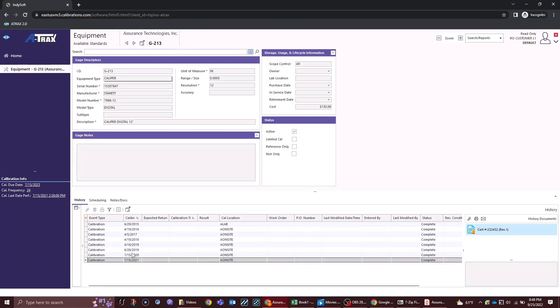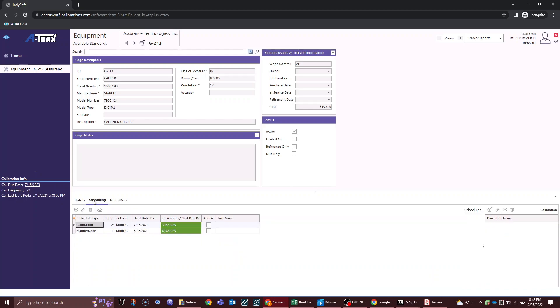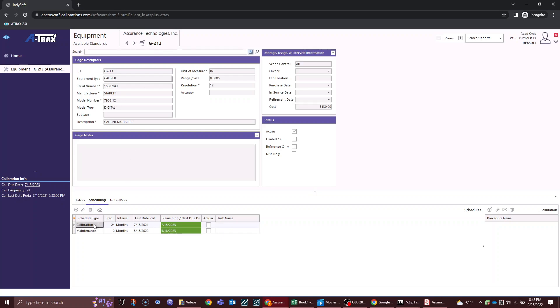That's how you would look at your history for individual gauges by clicking on the history tab. If I look at my scheduling for this gauge, I can see here I have a calibration schedule of 24 months and a maintenance schedule of 12 months, so it will alert me on these dates that these are coming due.